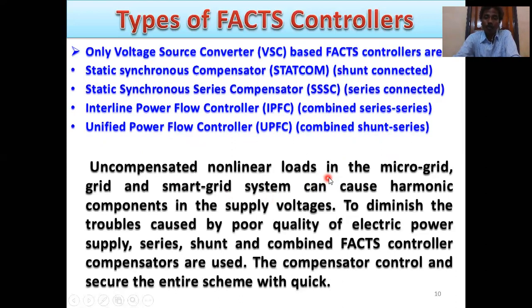Uncompensated nonlinear loads in the microgrid, grid and smart grid system can cause harmonic components in the supply voltage. To diminish the troubles caused by poor quality of electric power supply, series, shunt and combined FACTS compensator controllers are used. The compensator controller secures the entire scheme with quick response. That means when series connected, shunt connected, or series shunt connected controllers are used, they control power quality, solve different types of power quality issues, and mainly improve efficiency and reliability.